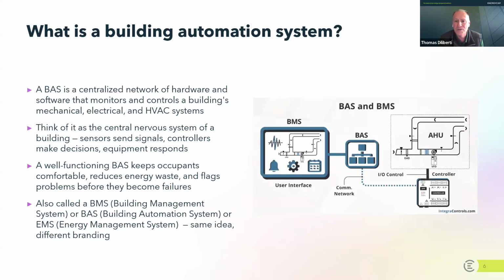The image here is of an air handling unit. So you want to think about your building automation system as the central nervous system of a building, but there's all these devices that are being controlled electronically, and at the end of the day, the building automation system is trying to keep people comfortable, and it's trying to manage your energy use and make sure the systems are running when they're supposed to and not when they're not supposed to.